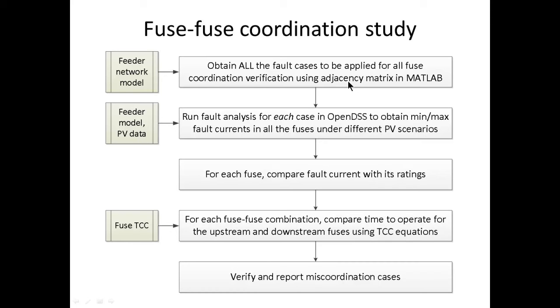So for a feeder of the size of Sandvik 4, we may have thousands of cases to run to study the fuse coordination along the entire feeder. I will use this simple example feeder that we've been considering to illustrate how we determine which fault cases need to be run for the fuse-to-fuse verification.